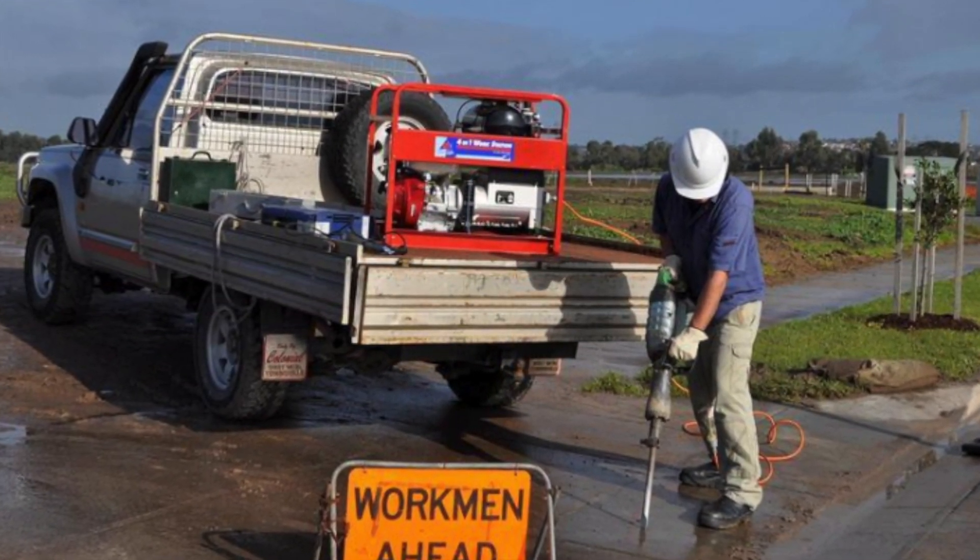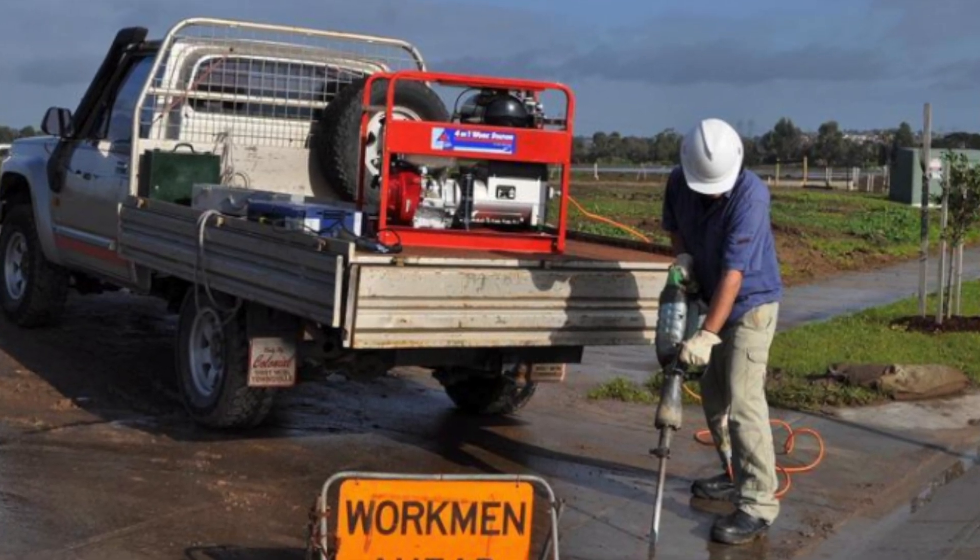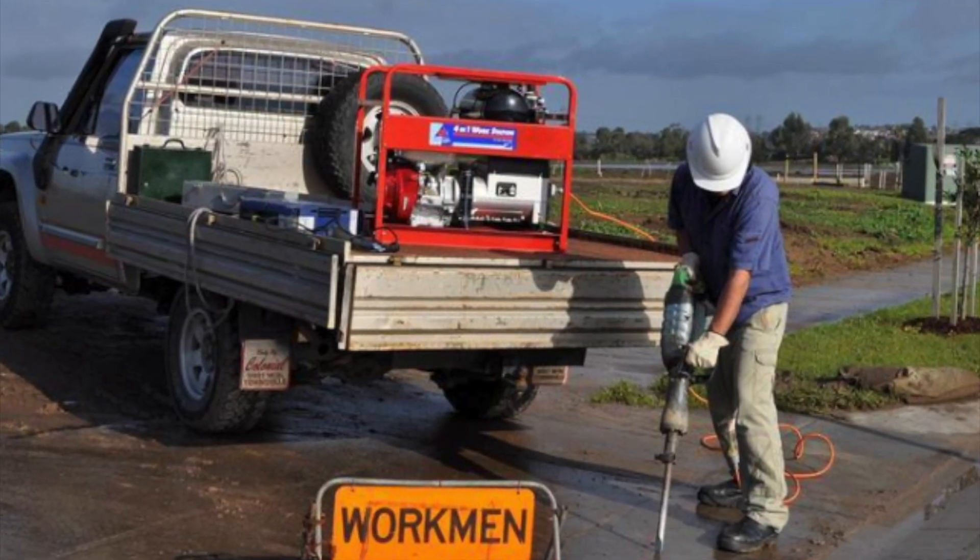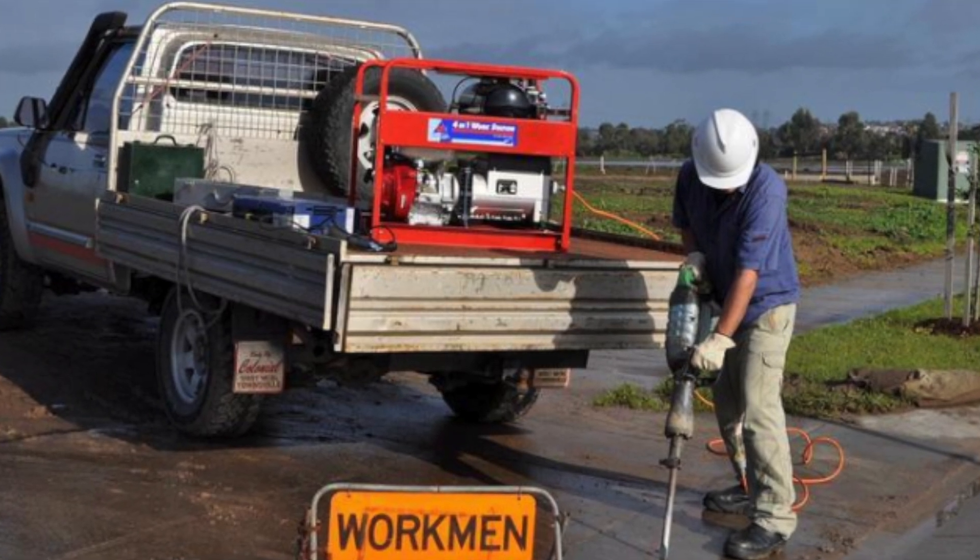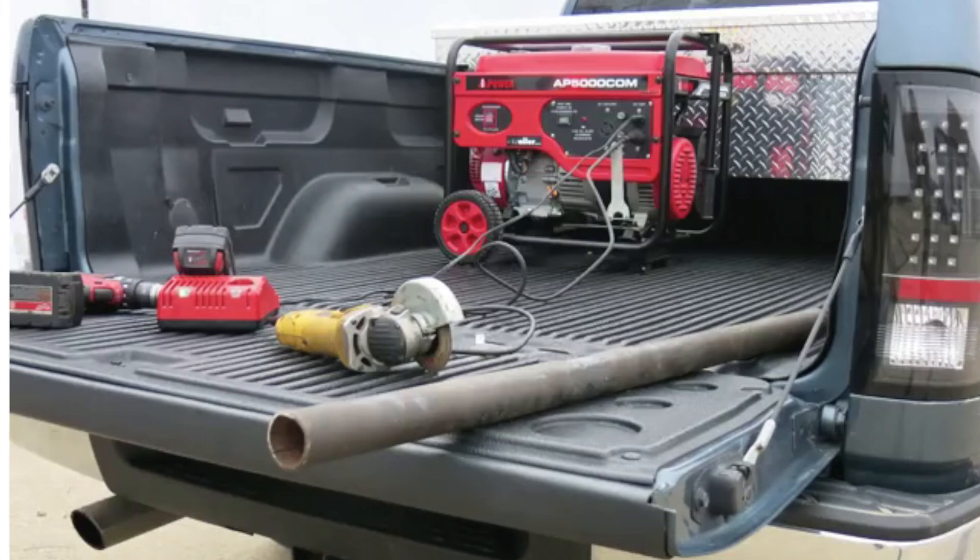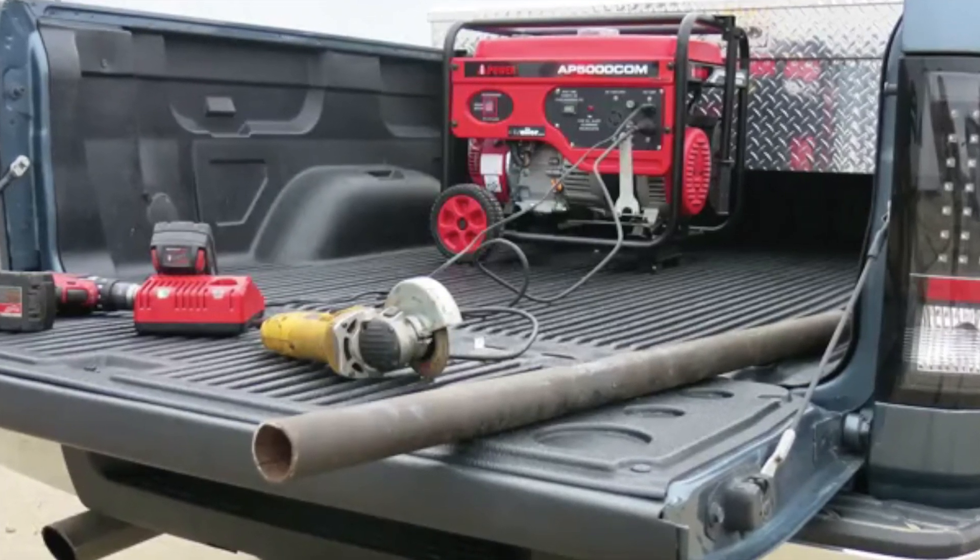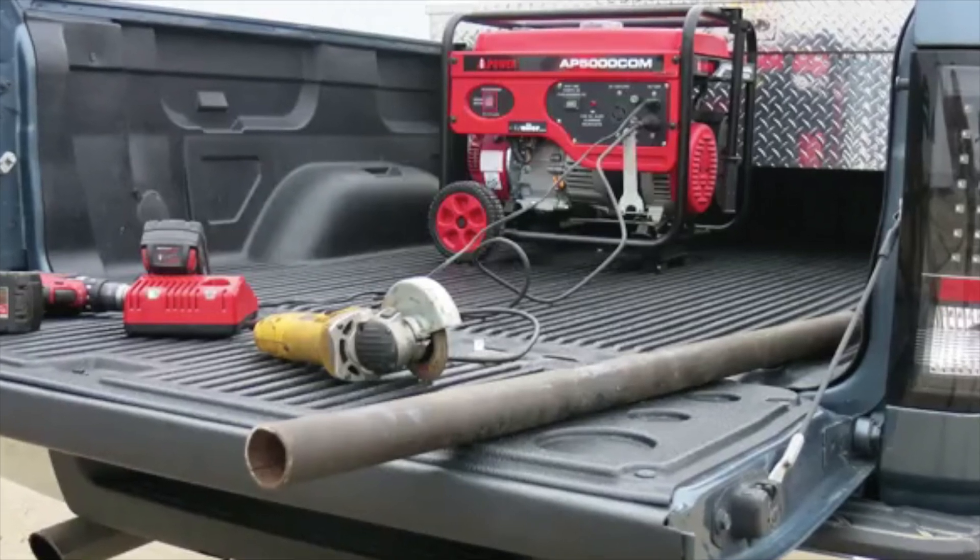Consider a generator sitting in the back of a pickup truck with several leads attached to it, with appliances or tools attached, and then a fault occurs. The RCD will not trip, and all attached earths to any equipment now is live, including any metal touching the frame of the generator.